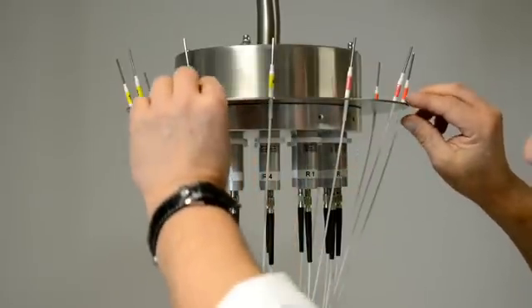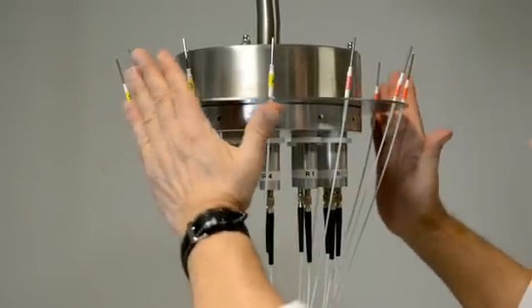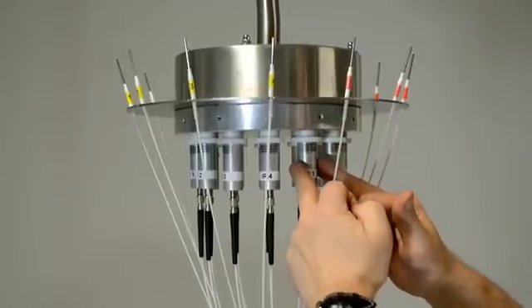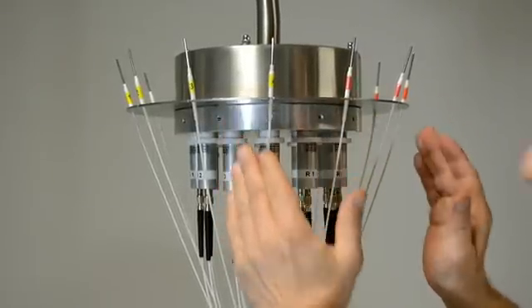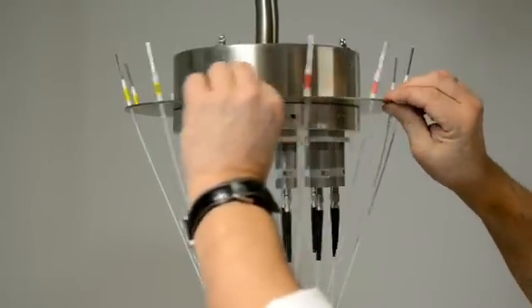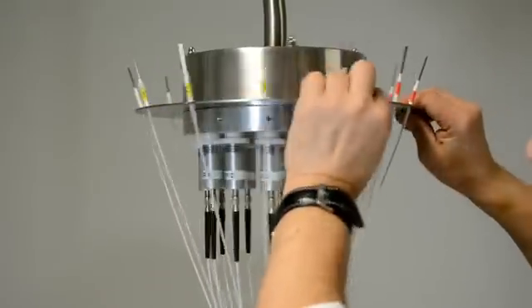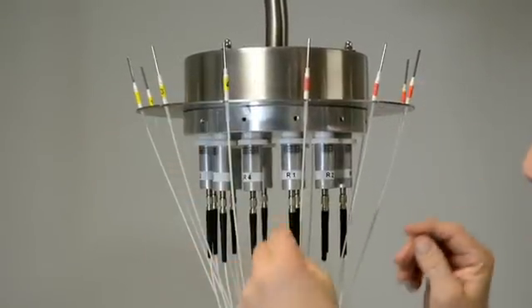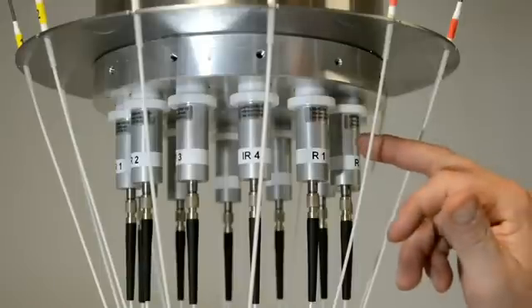The head is heavy and guarantees perfect cooling of the device, which guarantees long life of the laser modules. Especially green and blue modules produce more heat, so cooling of the modules is very important. I can move the head by turning, so I don't have to run around the patient.